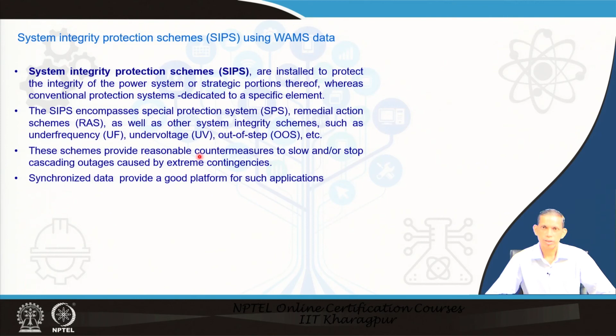The SCADA systems which are catering to these SIPs can be supplemented with wide area measurement systems, because that gives us a better scope for such applications. Let us see an example of how in the Mexico grid SIPs using synchrophasor data are being implemented. So, this is a part of the Mexico grid. Chicoasén, Angostura, this 400 kV line, there are parallel lines, a double circuit line, and there are a number of connections for the 115 kV network. So, what happens is that these 900 megawatt generations push power to the national grid, other portion of the system, through the double circuit line, and there is also a connection of the 115 kV line.